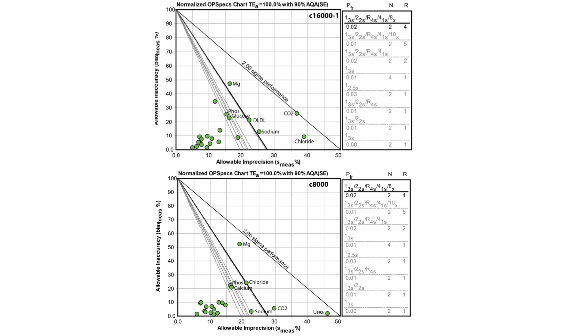So some of the sort of 6 sigma QC rules of thumb. If you're greater than 6 sigma, you can use fewer QC, use 2 levels of QC which meet the CLIA regulations, and wide limits, maybe 3, 3.5S, to prevent false alerts and spending a lot of time troubleshooting in the lab. If you're at the bottom, less than 3 sigma, you want to use maximum QC that you can afford in the laboratory. Maximize your preventative maintenance, your function checks, deploy your most trained and skilled employees.